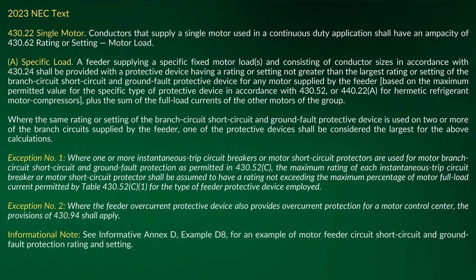Well, then you make a good point. If you come from an MCC, a lot of times the MCC has fuses in it. Mm-hmm. So then you have the feeder to the MCC, then the fuses, then you go out to your motor. A lot of times you hit a motor starter, and then you go from the starter to the motor or to the VFD or whatever it may be. A lot of times they fuse ahead of the VFD. So to me, that's all branch circuit from the MCC to the VFD. Sure, if it's a single motor you're going to.